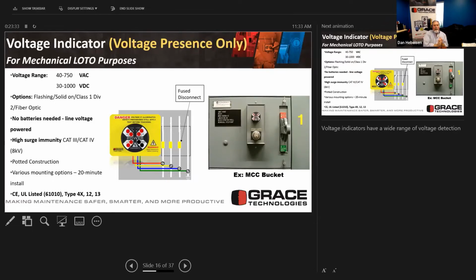Where would a permanent electrical safety device be mounted? In this circumstance, we've got a fuse disconnect. We've got your A, B, and C phase, as well as the ground. A couple of different features available are flashing and non-flashing. Most customers prefer the flashing because it attracts a little bit more attention. But one unique thing about this is it's fed from the line voltage. And that voltage can be anywhere between 30 volts all the way up to 1,000 volts DC or 40 volts to 750 volts AC. And this device is simply comparing phase to phase and phase to ground.